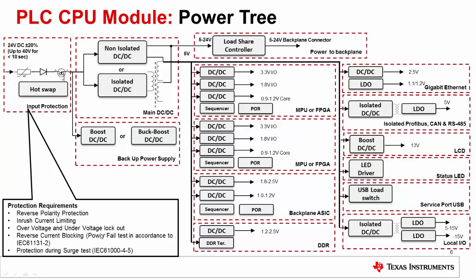Over voltage and under voltage protection during external power supply faults, reverse current blocking during the power fail test in accordance with the IEC 61131-2 standard, and load protection during the surge test, which is conducted on the input 24V supply line.